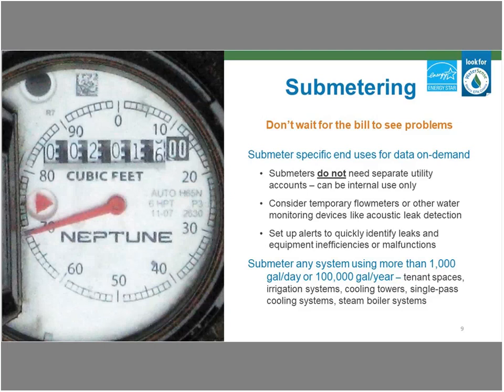When identifying areas where water submeters should be installed, a good rule of thumb is to submeter any system with an anticipated water use greater than 1,000 gallons per day or 100,000 gallons per year. So large mechanical systems that use a lot of water, like cooling towers or steam boilers, are really great places to consider submetering to help track your consumption related to these specific systems. We also recommend submetering alternative water sources such as gray water or rainwater collected on site, so you know how much water you've collected and used, and how much domestic water you're really saving. And if you are doing metering and submetering, I certainly want to put in a plug for Energy Star Portfolio Manager. This is a great place to track and monitor your water bills and meter readings.